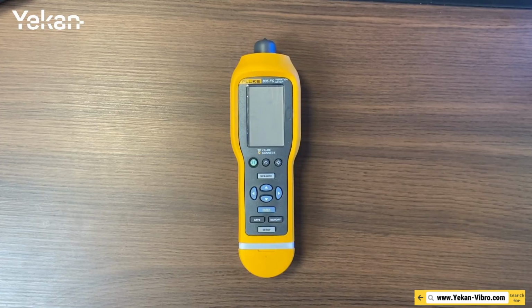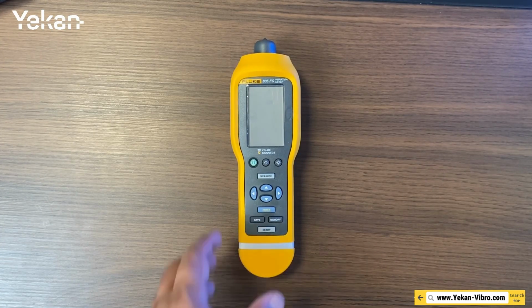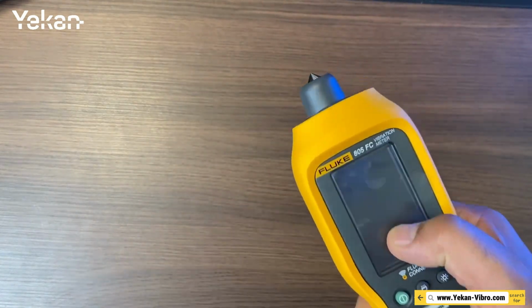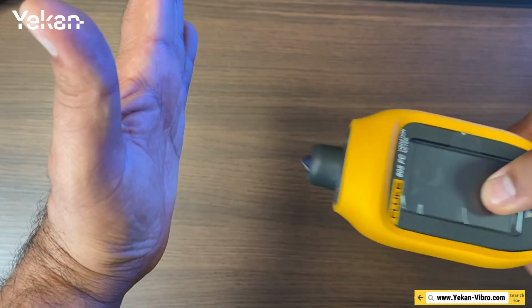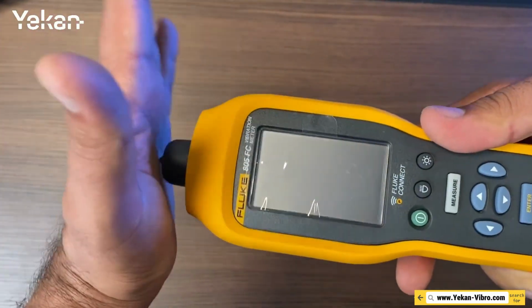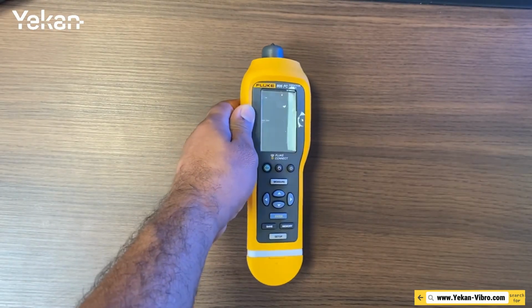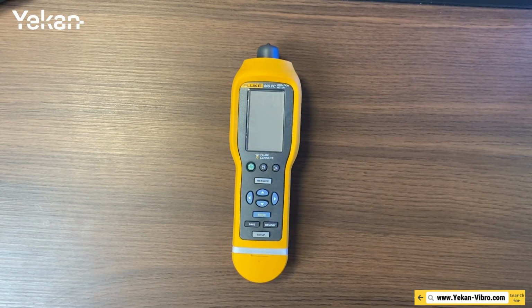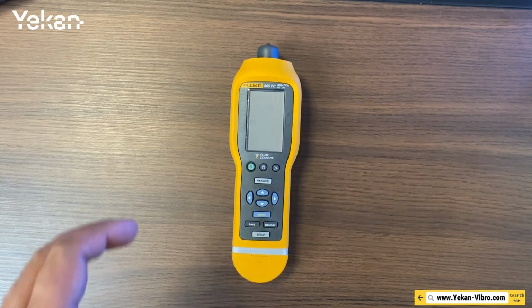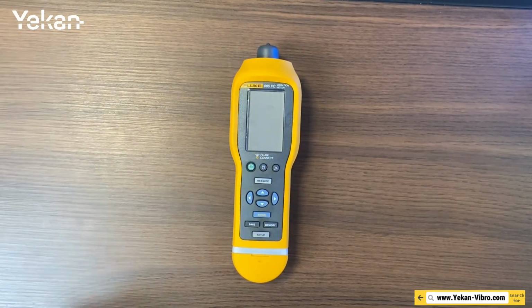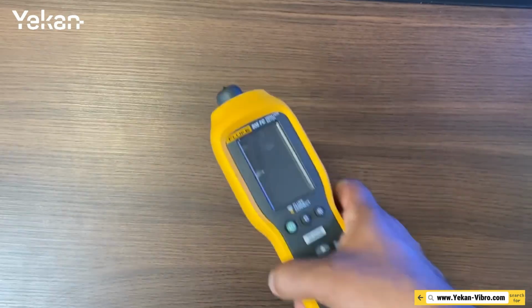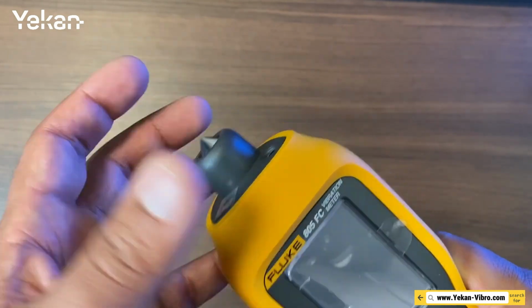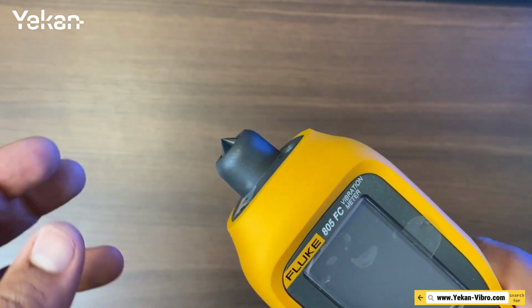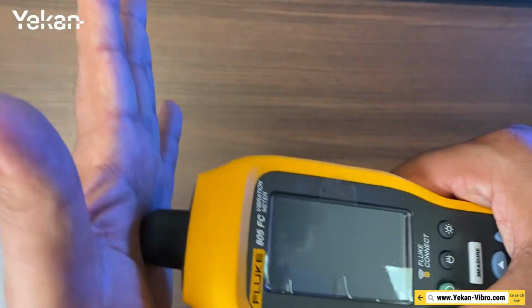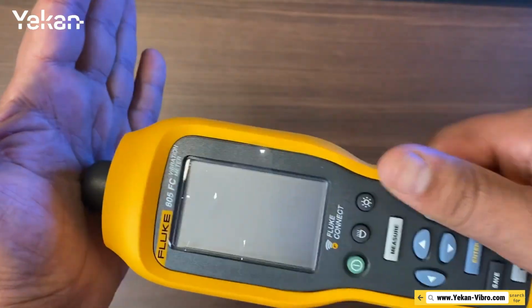If I want to talk about this device, it does not have a separate sensor. It is a pen-type device, meaning wherever you want to measure vibration, you have to press the device body directly against the machine's surface. I can say this is one of the best models I have seen in this category. There are many vibration measurement devices; most of them have a cable, a separate sensor, and a magnet. There are also many models, mostly Chinese, that do not have a separate sensor and instead have the sensor integrated and attached to the device. One problem with those is that depending on the user's applied force and the way they hold the device, different people may apply different pressure, resulting in different readings.